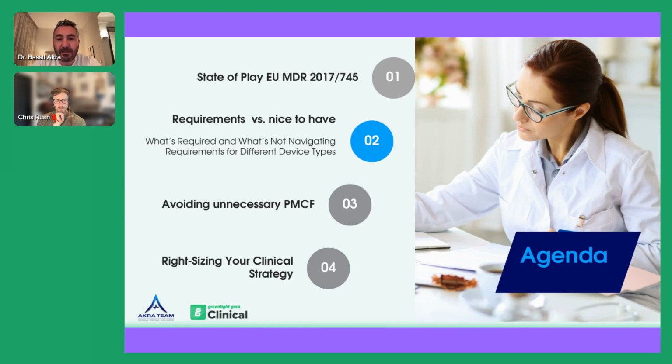Some of them are still doing post-market clinical follow-up under the directive to collect data, to enable them to submit with full evidence, re-establish compliance and show that they are in compliance with the new legislation. This is costing a lot of time, and not just the clinical data. There are other aspects influencing design and manufacturing that are leading to delays.